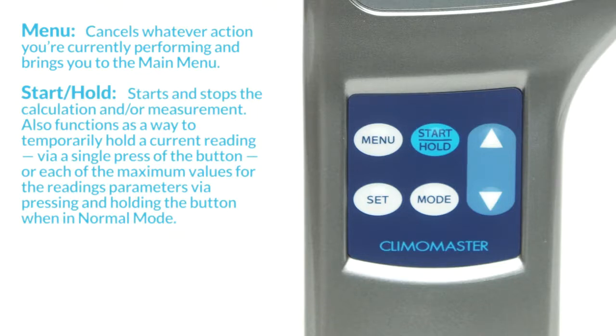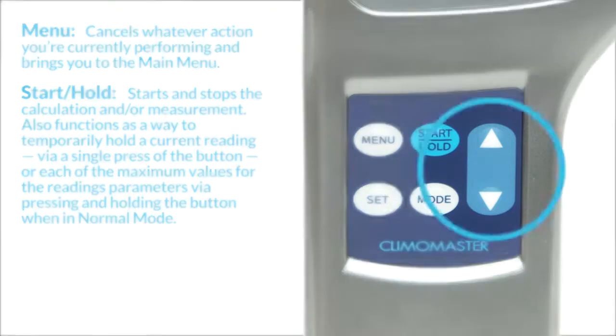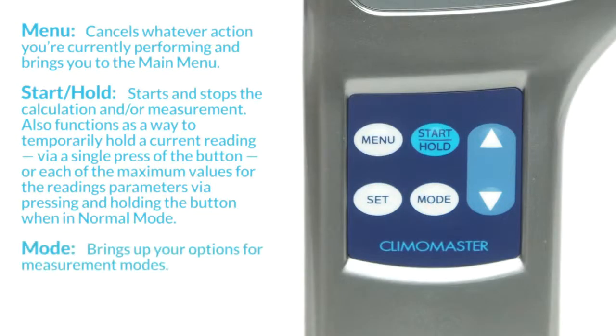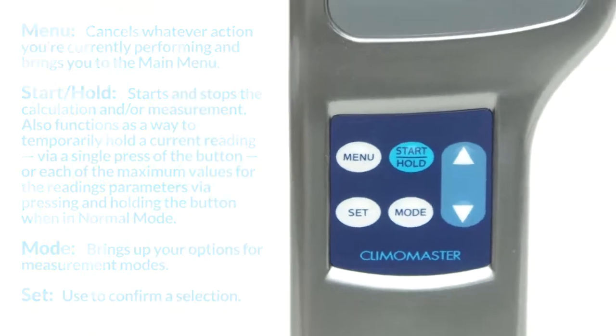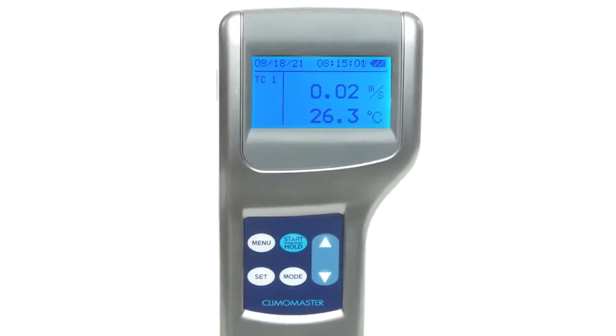It also functions as a way to temporarily hold a current reading via a single press of the button, or show each of the maximum values for the reading parameters by pressing and holding the button when in normal mode. The navigation buttons can be used to scroll through any of the menus that pop up on screen. The mode button brings up your options for measurement modes, and when you want to make a selection, press the set button. Just to clean our slate before our first measurement, let's perform a zero adjustment procedure.